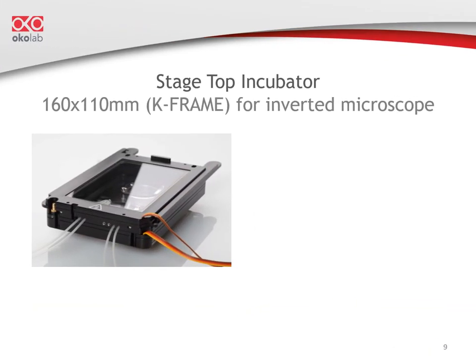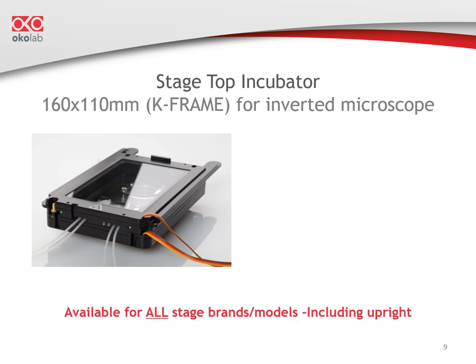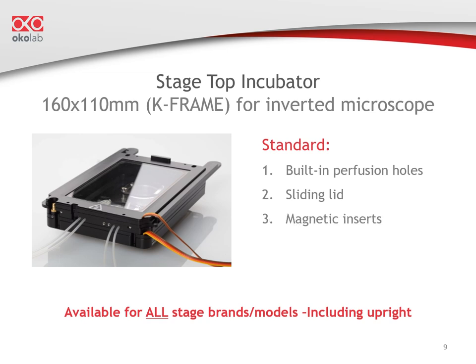To illustrate the microenvironmental chambers, I will use a K-frame for inverted microscopes as an example. A K-frame simply fits a microscope stage with an opening of 160 x 110 mm. Chambers for all stage brands and models, including upright, are available. OkoLab K-frame chambers have built-in perfusion holes that come plugged with small screws — you can unplug them if you need to do perfusion. The lid slides open, and you do not have to put water inside the chamber to provide humidity. The sample is placed in the chamber using a magnetic insert.